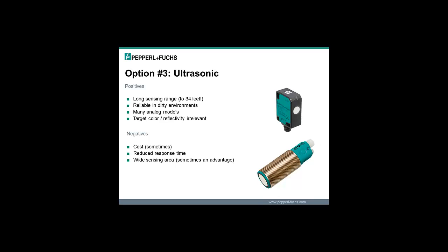And also there's a wide sensing area, and that sometimes is a negative if you're trying to shoot through an area and detect a target in a very space-restricted area with a lot of obstructions. But it can also be an advantage if you want to get an average over a wide area or cover a wide area, like for collision avoidance or something like that. So those are the positives and potentially some of the drawbacks to ultrasonic sensors.